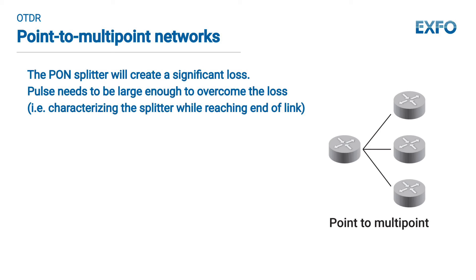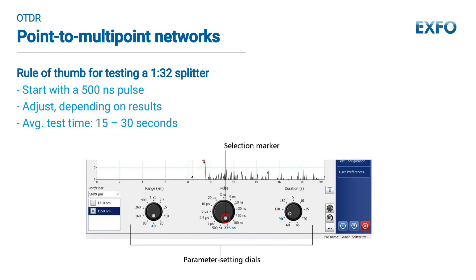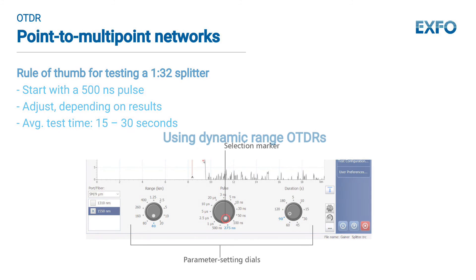Real-time mode is not useful in point-to-multipoint networks. A good rule of thumb for testing a 1 by 32 splitter is to start with a 500 nanosecond pulse and then adjust slightly one way or the other depending on the results. The average test duration should be at least 15 to 30 seconds. Keep in mind that the longer the average test duration, the better the performance — this is a compromise to consider.